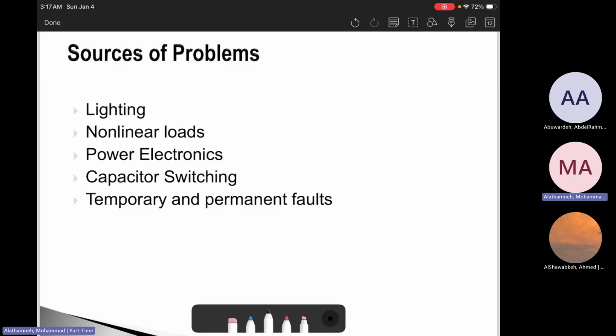The other thing, capacitor switching. Capacitor banks, again, are used to make a power factor correction and voltage support, supply reactive power. But this switching can create transients and resonance. The other thing, temporary and permanent faults. Faults can produce sags, interruptions, and sometimes impact the unfaulted phases. Clearing the faults and recloser can create repeated sags. As we mentioned in the previous couple of lectures about the recloser, the recloser can be turned on and turned off multiple times. This makes more voltage sags, repeated events of sags.